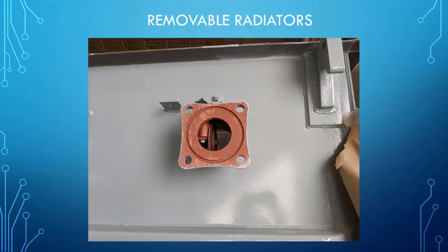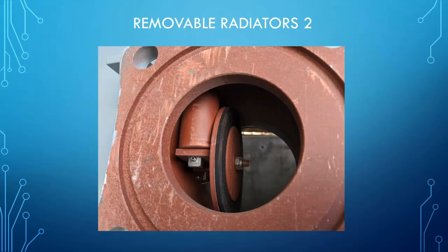And you can see how these work. There's a hole for a bolt, and then there's a ball valve. But it's not a ball valve, it's another kind of valve. And here's kind of a close-up of what's going on. So if the radiator needed to be removed, you would simply close the valve and remove the radiator, and then you could move the transformer a lot easier.